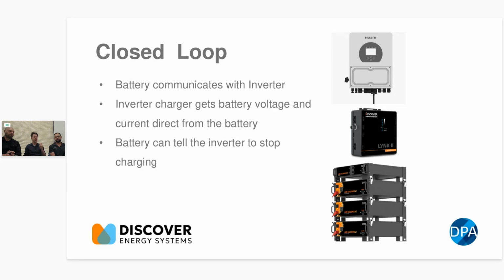So what that means is that at their different states of charge, you can get more or less charge in and out of the batteries. If you don't have comms, you just have to set a value that works for the entire range. But as soon as you have comms, in the middle of the range you can pump in or pull out as much as you like. Towards the top and bottom, you've got to be a bit more careful, so we can dial that back. That means you can actually charge the battery at a higher rate because that maximum value can be higher. Does that fit?